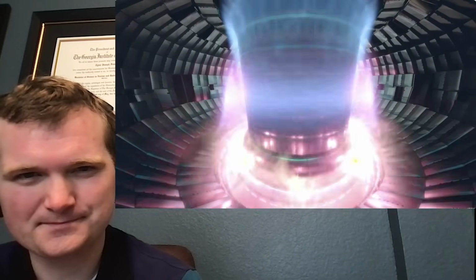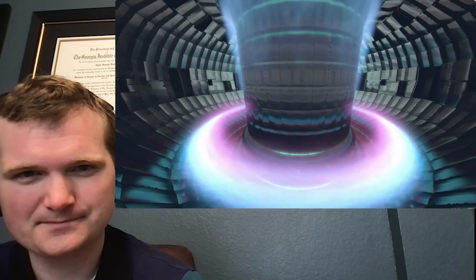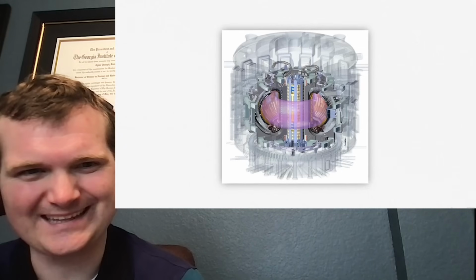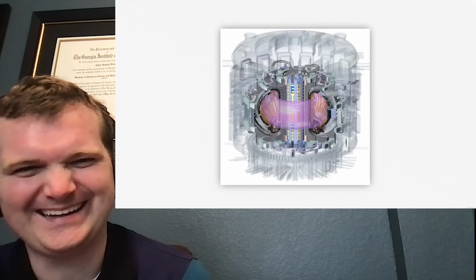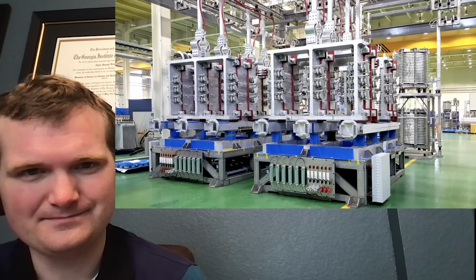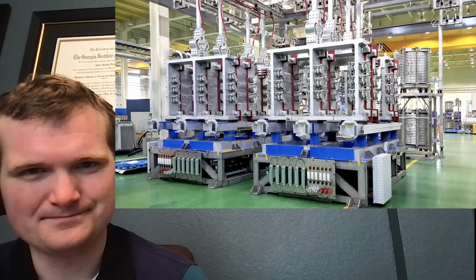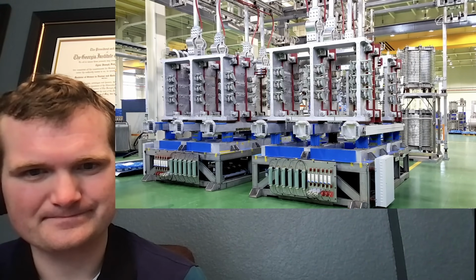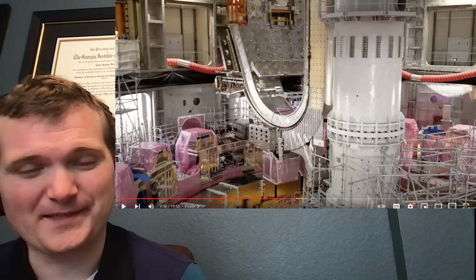Once energized, those magnets can collectively store upwards of 50 gigajoules of energy in their fields, though. So you also need to get rid of that energy if the magnets lose superconductivity, called a quench. Fast discharge units, located in this building, allow ITER to dissipate that stored energy as heat in a matter of seconds. Yes, you would need something for that much energy.